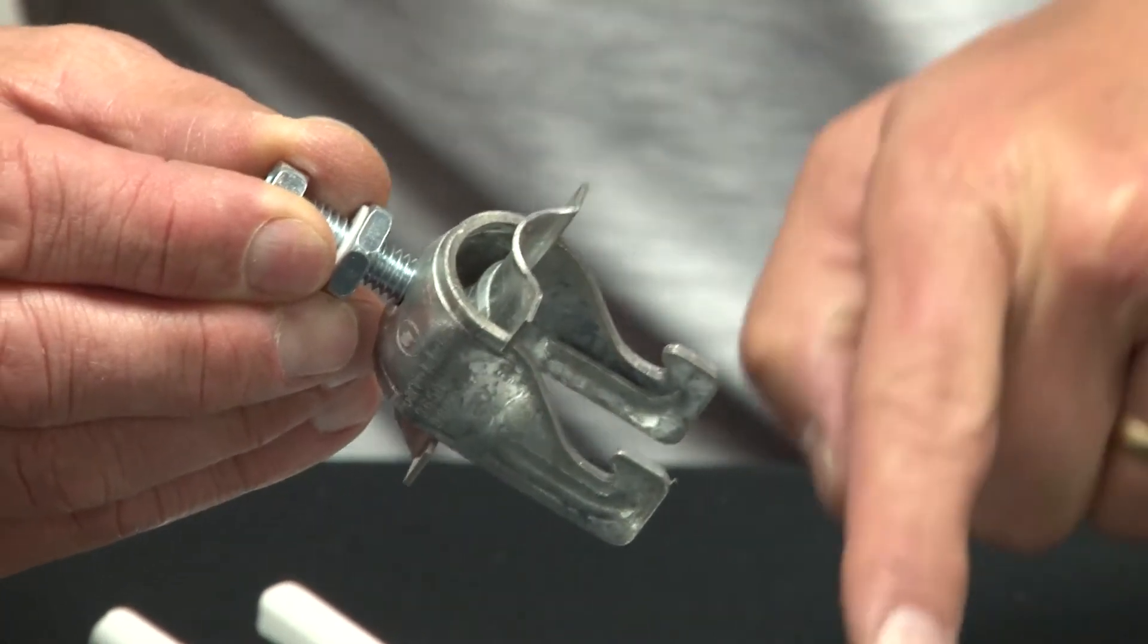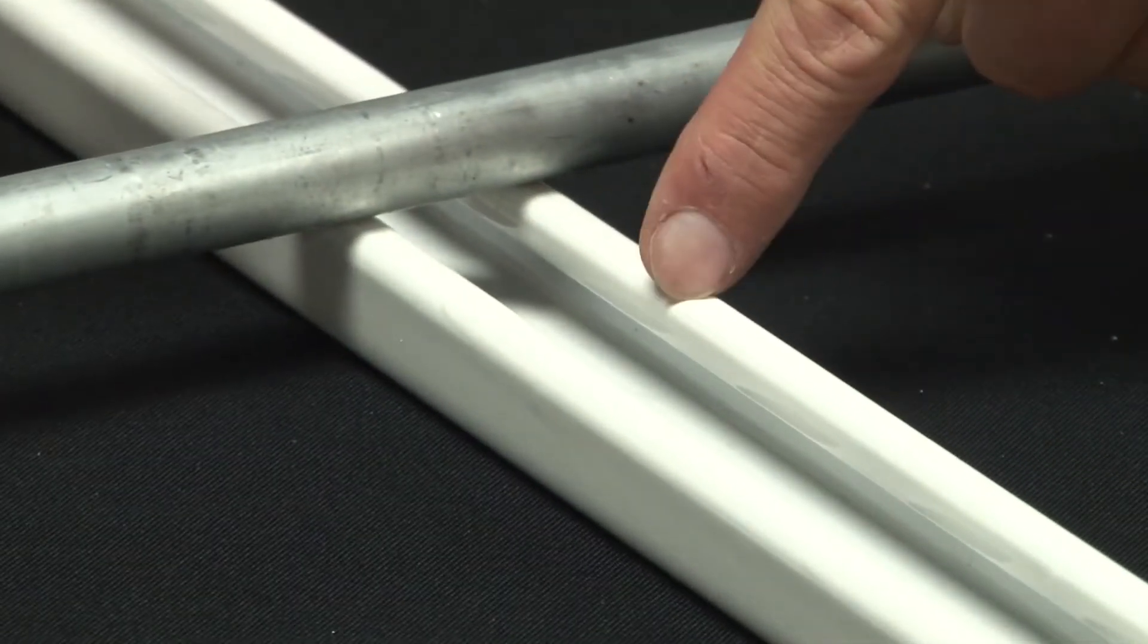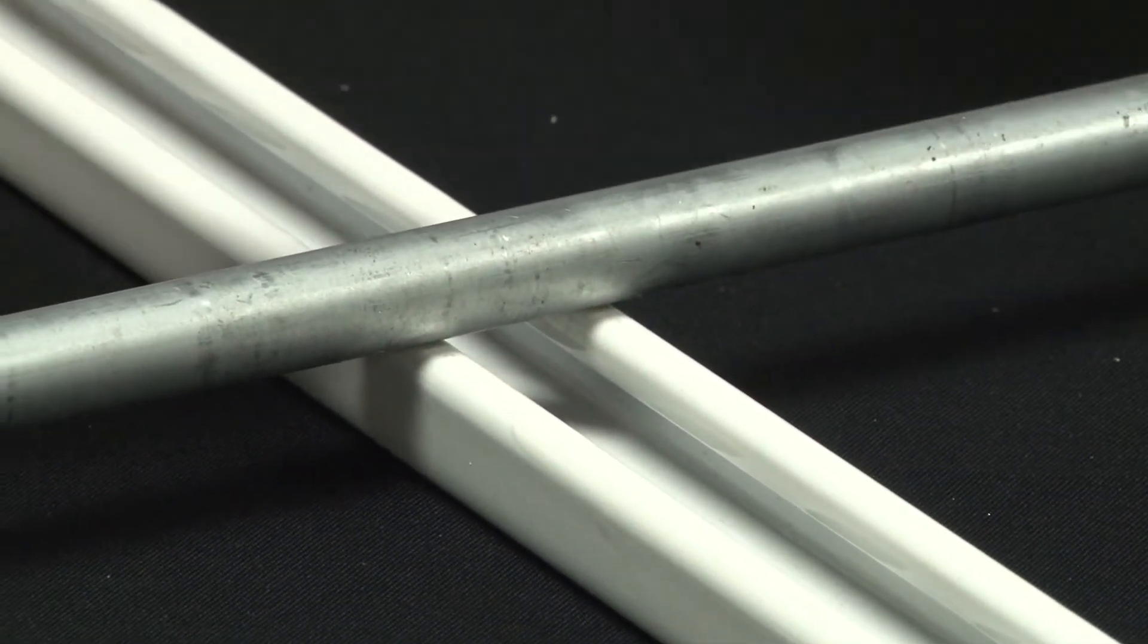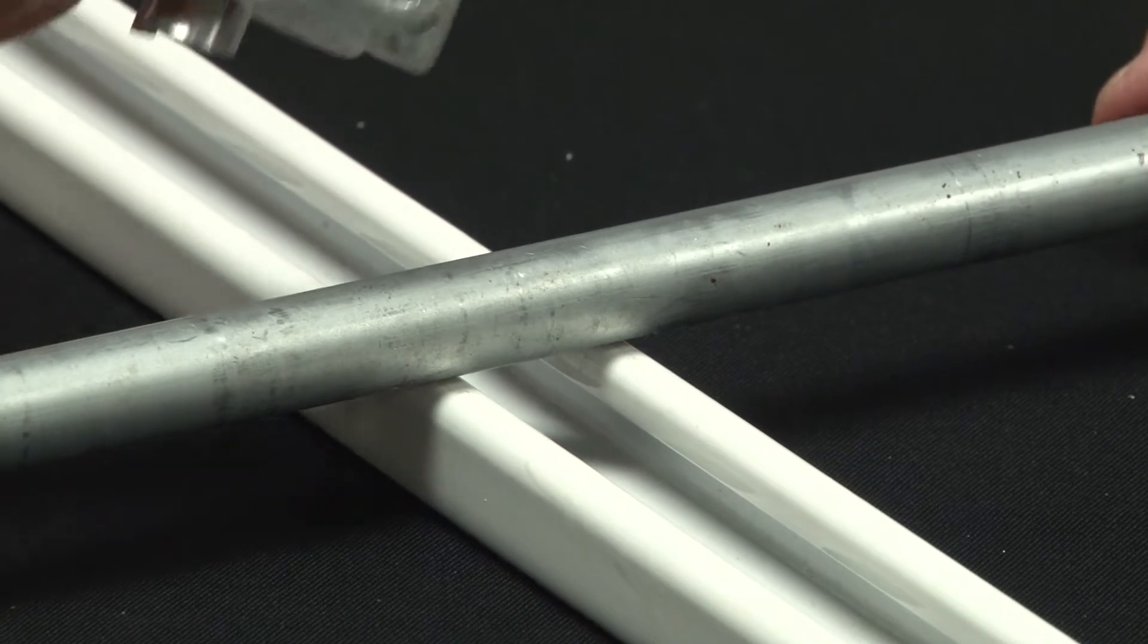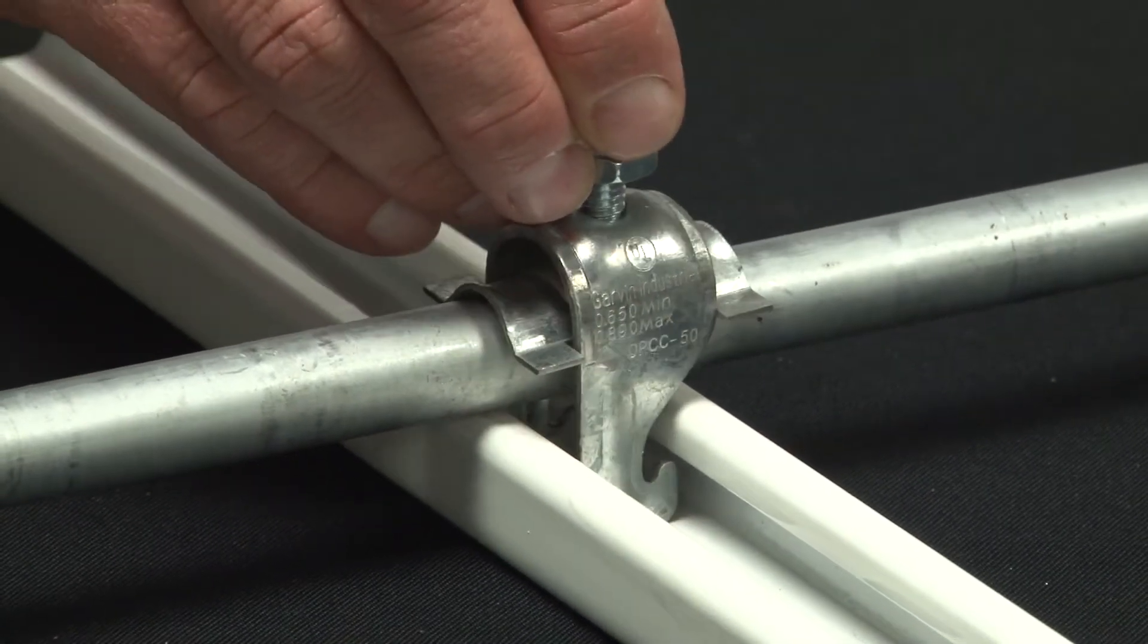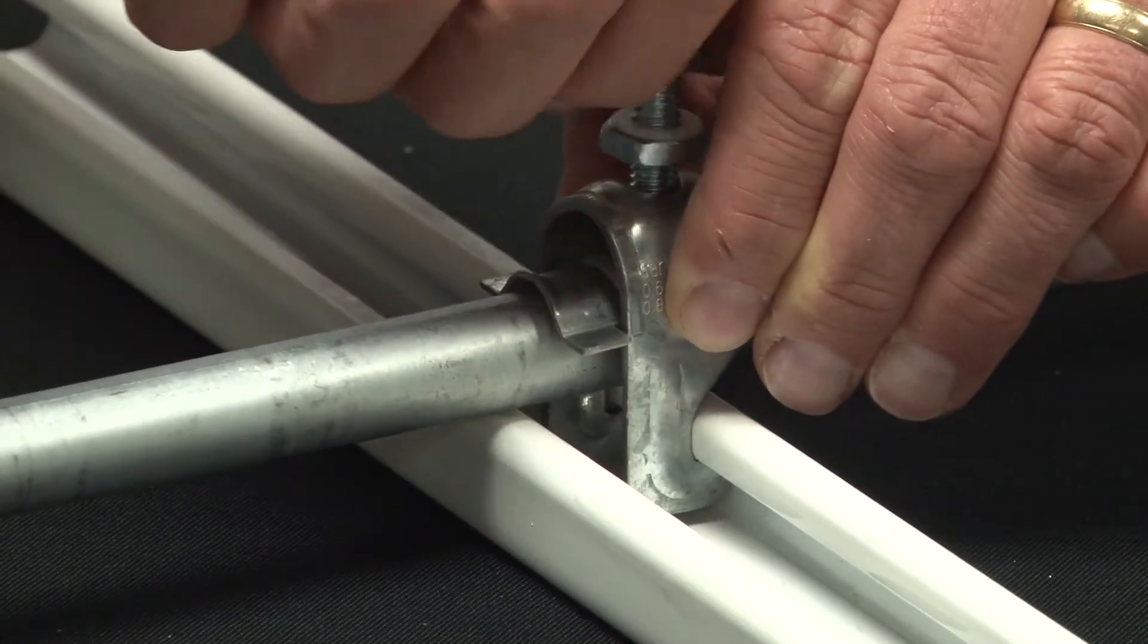You simply align the hooks with the interior edge of the unistrut and then tighten the bolt down, aligning the cradle with the conduit. So you slide it in, swing it over, align the cradle, and then screw it down.